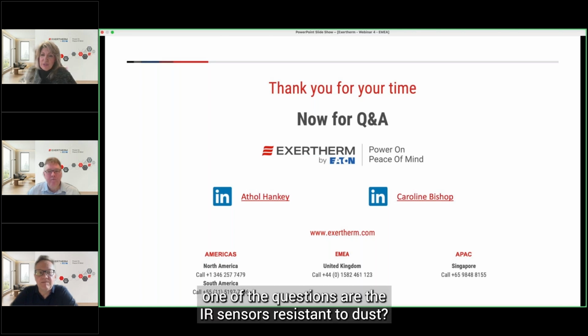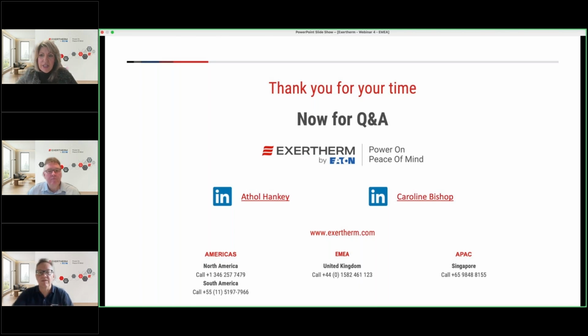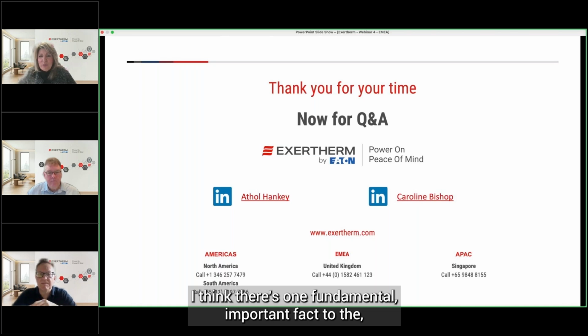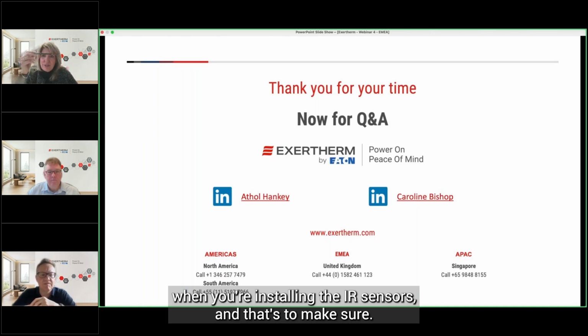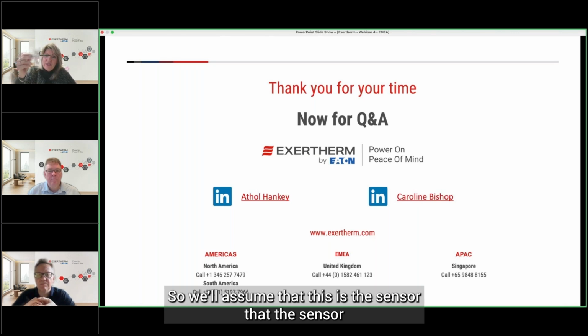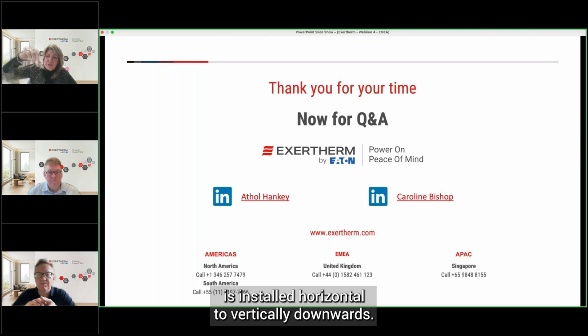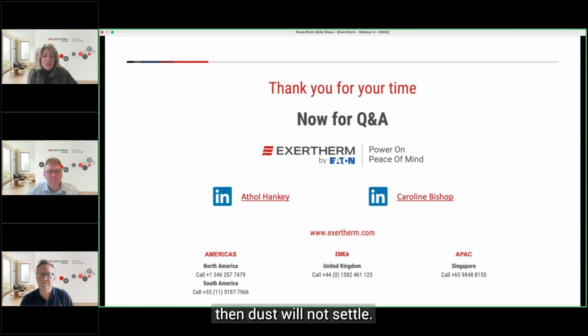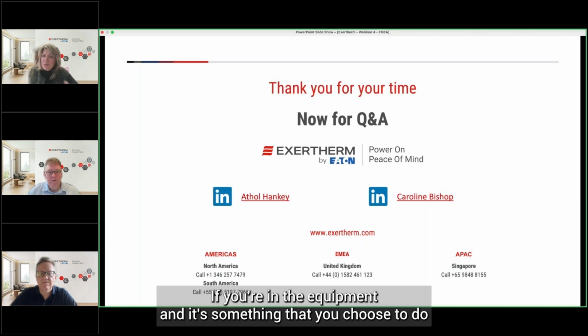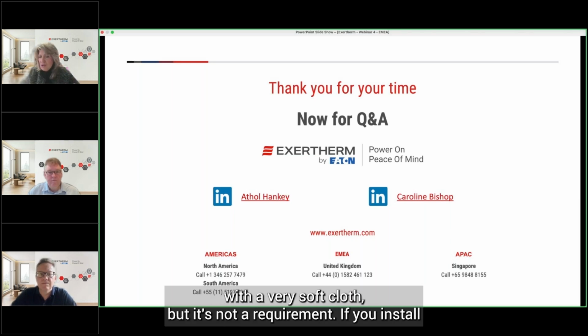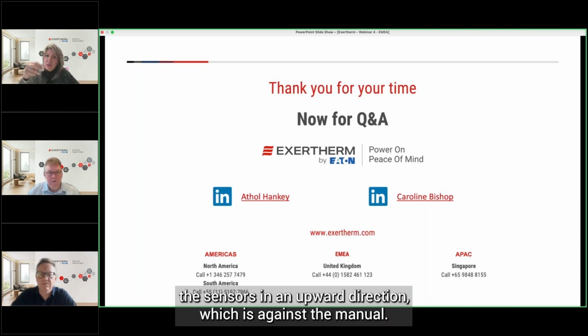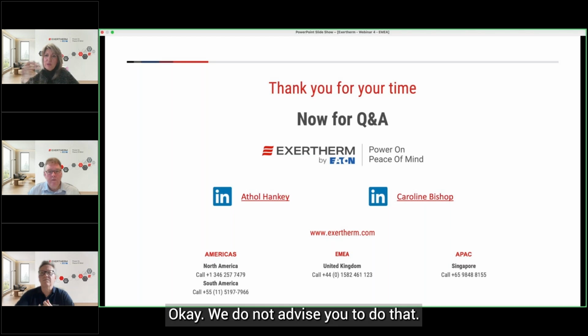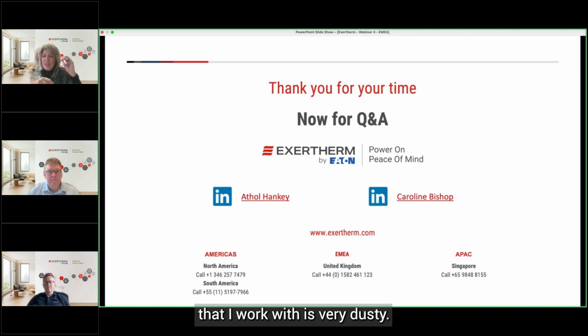I noticed a question: are the IR sensors resistant to dust? One fundamental factor when installing IR sensors is making sure the sensor is installed horizontal or facing vertically downwards. In those positions, dust won't settle, so you won't need to do any maintenance or dust it, though you can wipe it with a soft cloth if you choose. It's not a requirement. If you install the sensors facing upward, which is against the manual, we don't advise that, especially in the very dusty regions I work in.